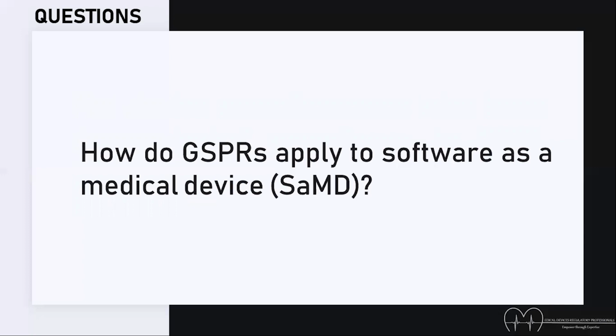What we see sometimes is that it's difficult for notified bodies to understand the validations of software, because they are linked to validation of equipment that is being controlled, or where there's a link to the hardware, and that is part of the validation. So make sure that even if it's combined, if it's a system approach that you've validated, sufficiently clear evidence on the software part is provided in your technical documentation. Then, in terms of the GSPR itself, maybe logical elements, but pretty black and white.